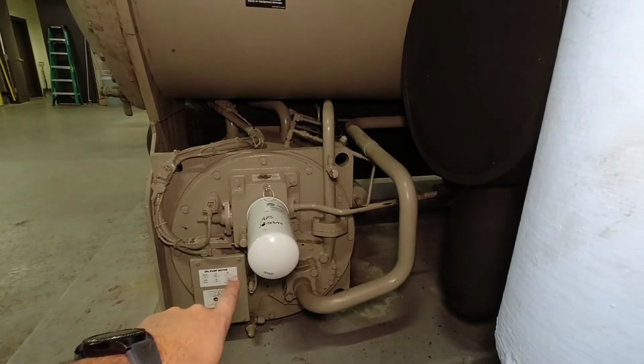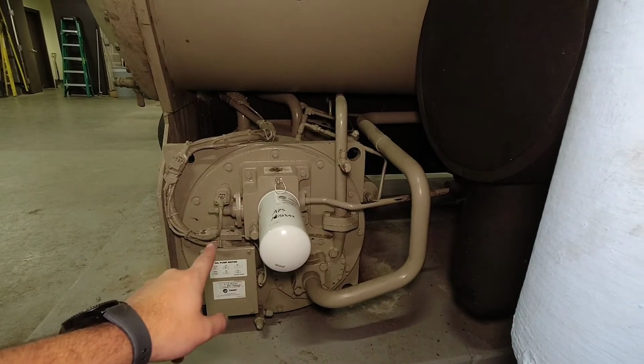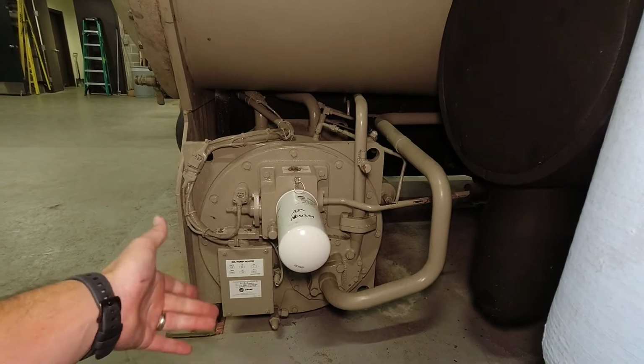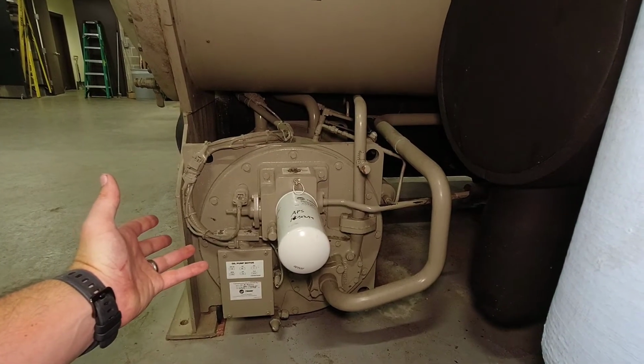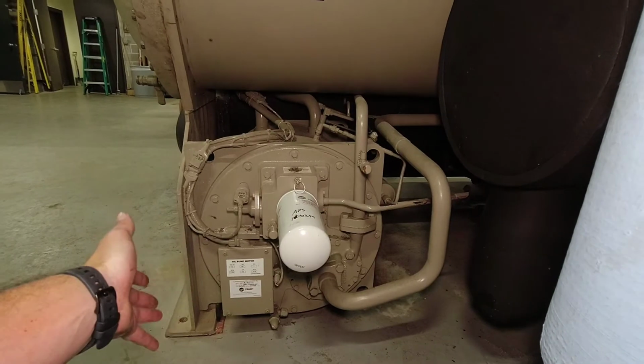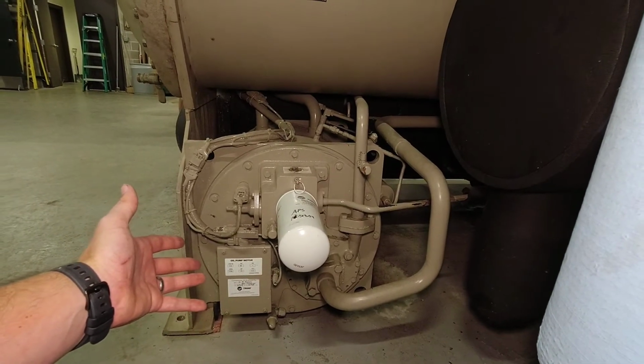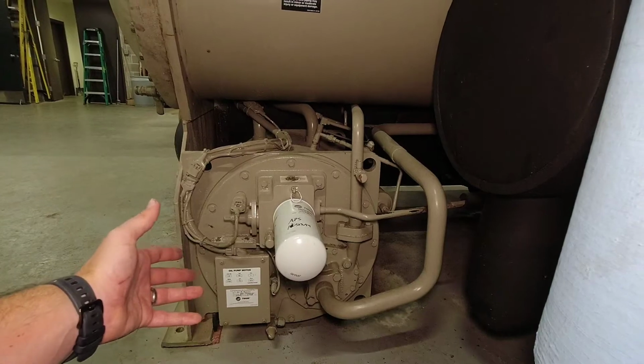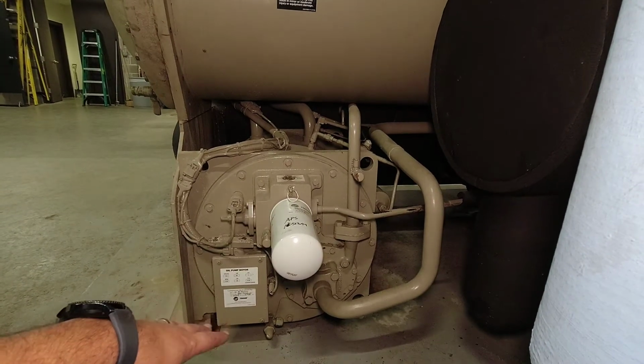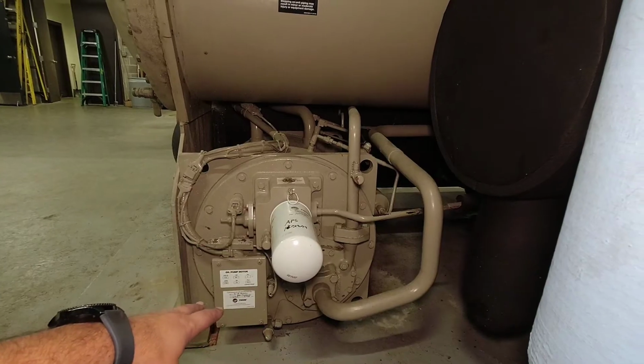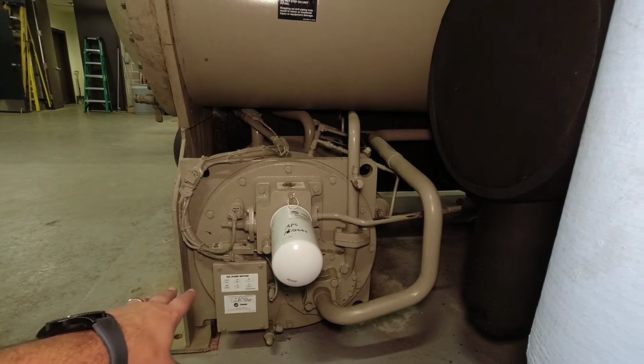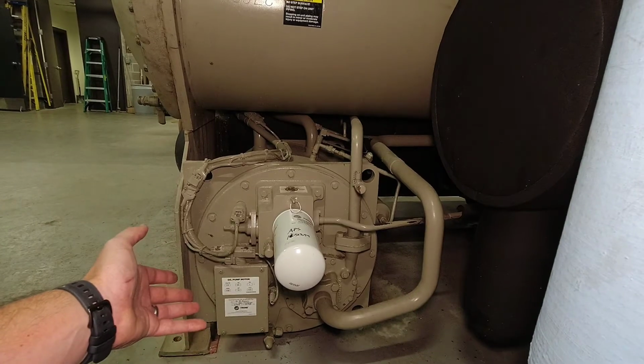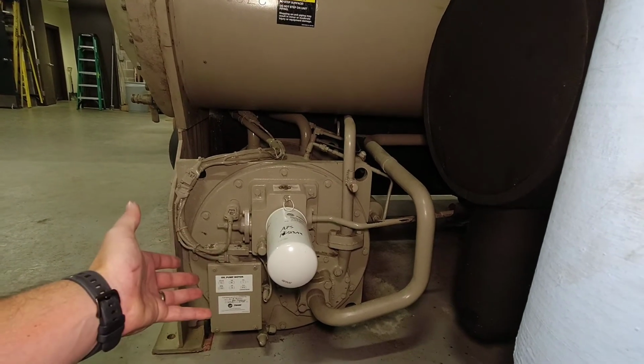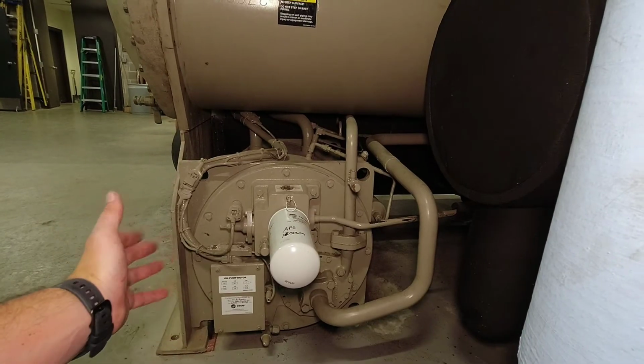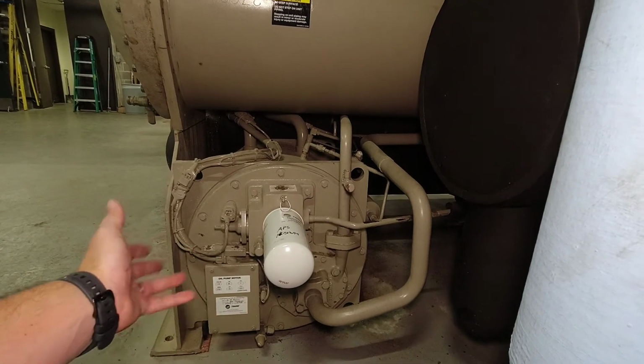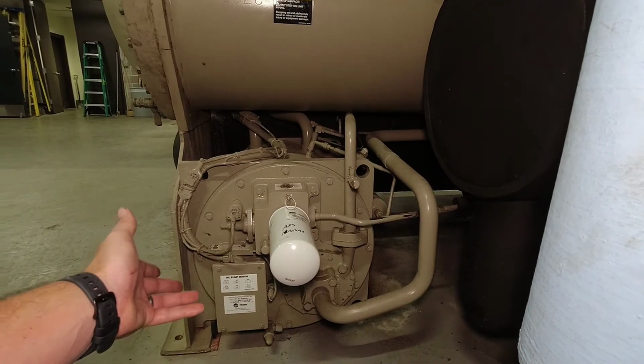So inside of this oil sump, you've got a motor and a heater. The heater keeps the oil temperature up above 120, and I believe it cuts out at 140. So 120 to 140 is the optimum temperature range for the oil. Typically the oil heater will only run when the chiller is off, and is trying to maintain a 120 minimum. Then once the chiller turns on and gets online, usually the motor and the operation will have generated enough heat to keep the oil temperature up.